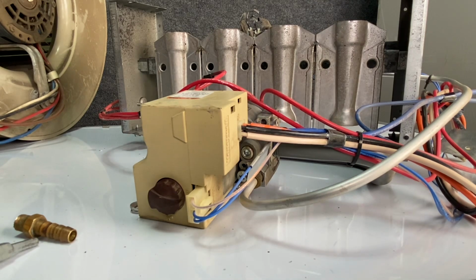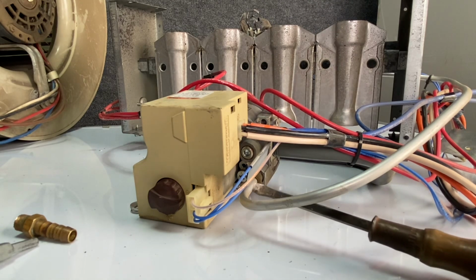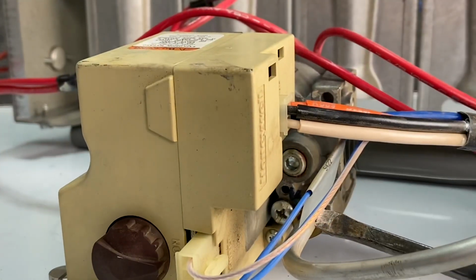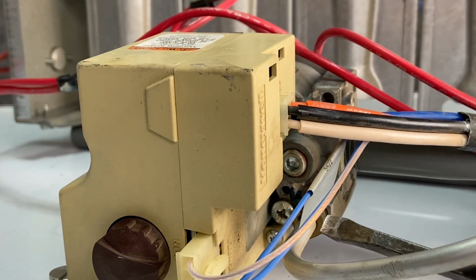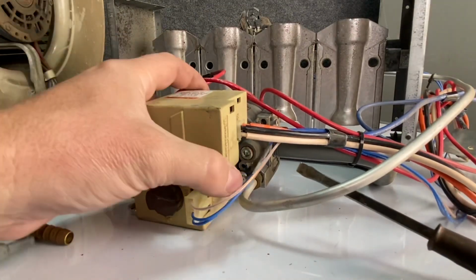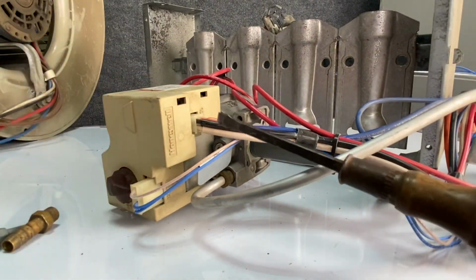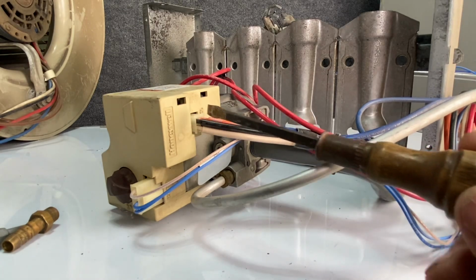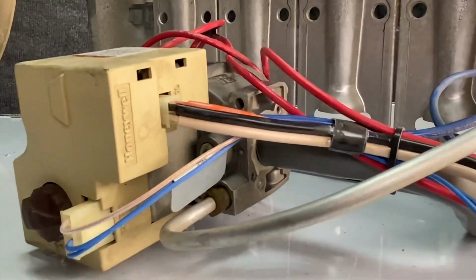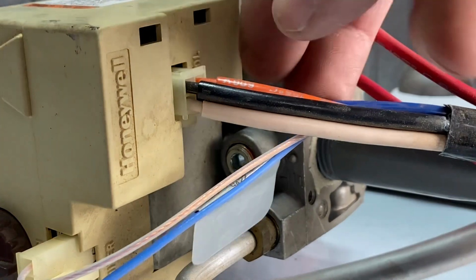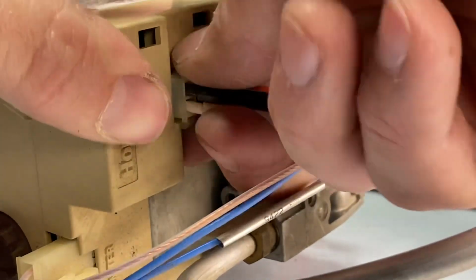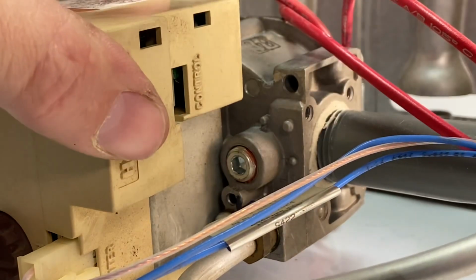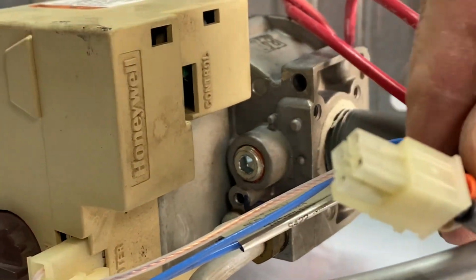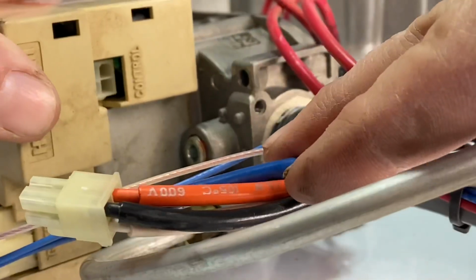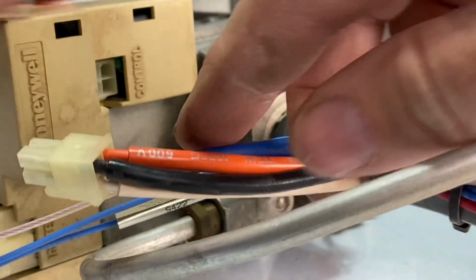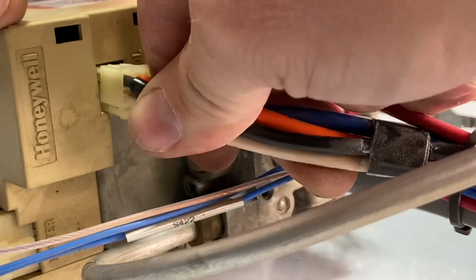On the back side, we also see this tube right here. This is our pilot tube, so this is what's sending gas to that intermittent pilot. And then on the side as well, this is what's going to our control board. The control board communicates to this, and it's just simply a square plug. We have a little keeper on it as well. If I just press that little keeper, this unplugs, and we have the 4 wires on this. So it's quite a simple little control, but inside of here is also a separate control board. Just plug this back in.